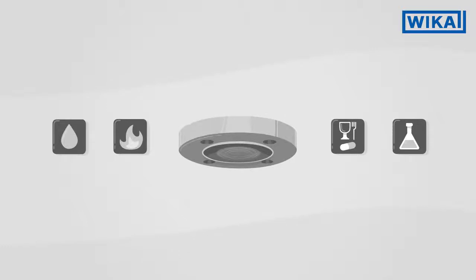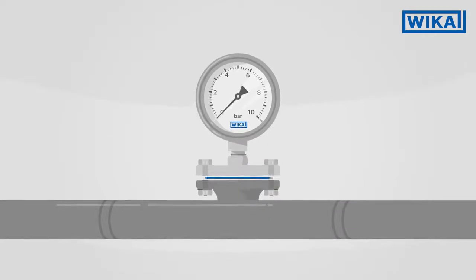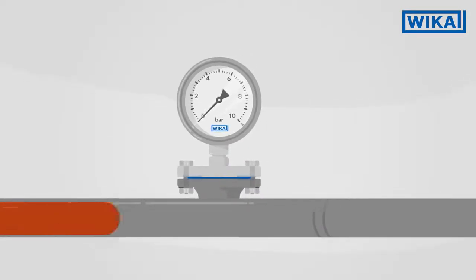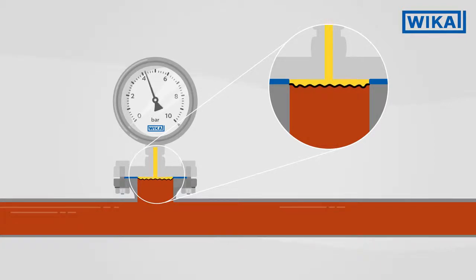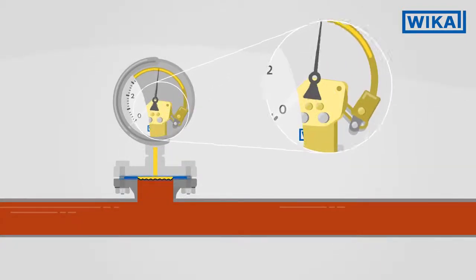The function is always identical in both cases. The diaphragm seals separate the medium from the measuring instrument with the aid of a fill fluid. Inside the diaphragm seal, the pressure is transmitted to the measuring instrument.